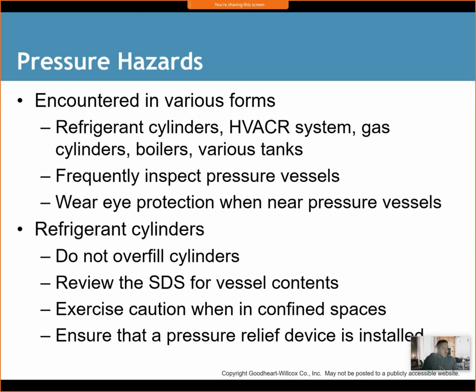When we're talking about refrigerant cylinders, we want to make sure that we don't overfill them. The reason is if we overfill them, there is potential for an explosion. When we fill up refrigerant cylinders, we fill them to 80% capacity. So what we're doing is removing refrigerant out of a machine and putting it into an empty tank, filling that tank to 80% of its capacity. The 20% left inside gives the refrigerant room for expansion. If we leave that tank at 100% capacity inside the back of our van, and it's 120 degrees out that day, it may potentially cause the tank to explode. We don't want that to happen, so we only fill it to 80% of capacity.